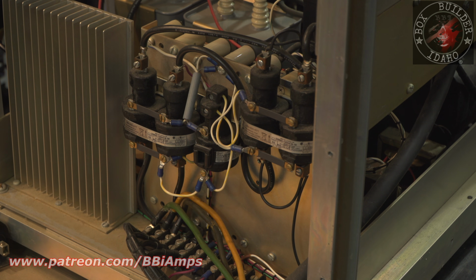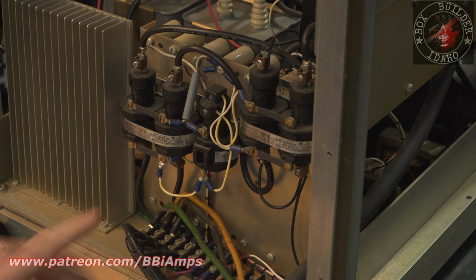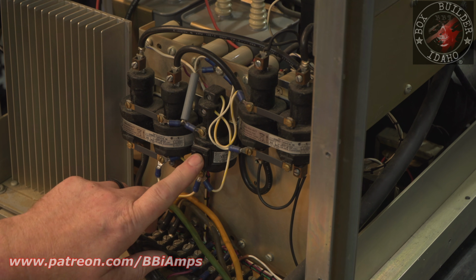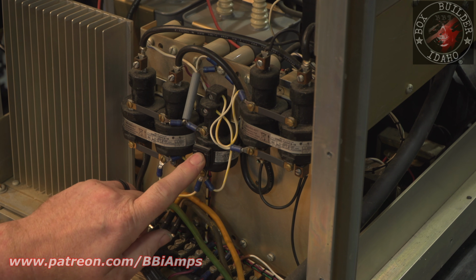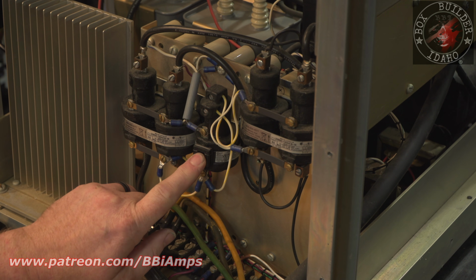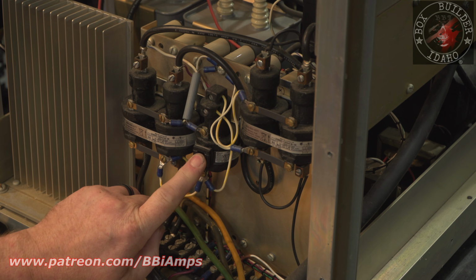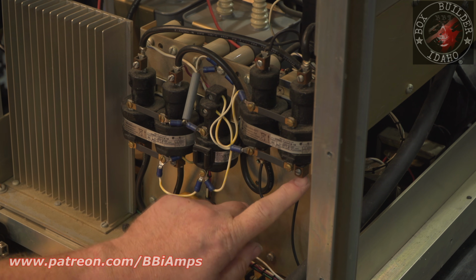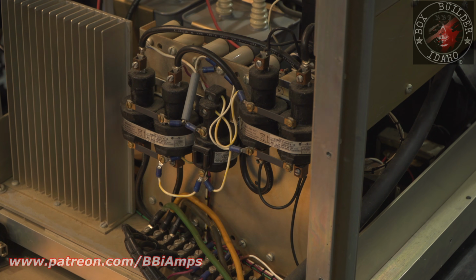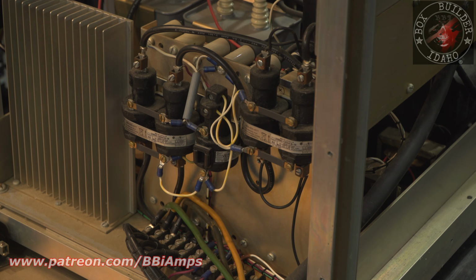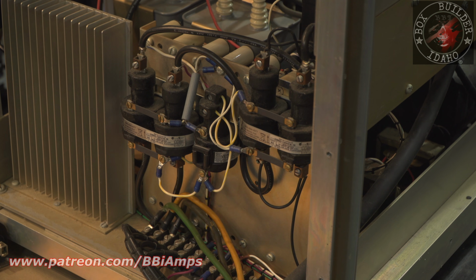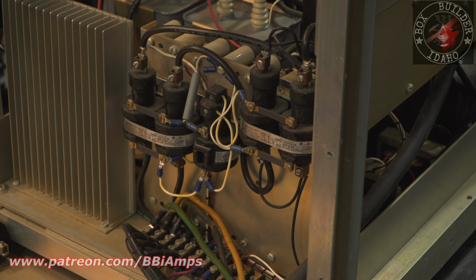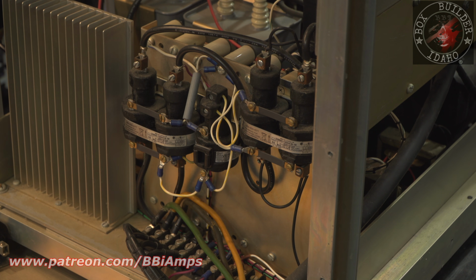When he changed this out, did he put it back together backwards? So how this should work is there should be a timer someplace, or a circuit that's looking for some kind of reference voltage and based off of time and current draw, and this contactor will close. Because right now this lead's jumpered to here, and this lead is jumpered to here. This should be over here. And this is what closes the second side of the single phase, the other leg of it. That's wired wrong.